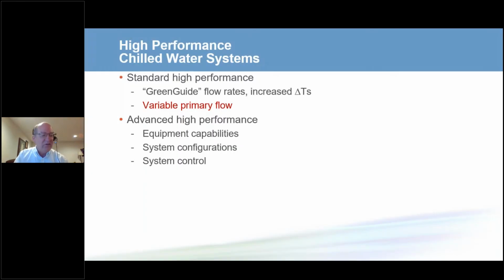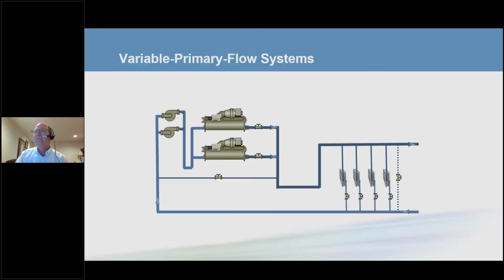The next thing we're going to talk about is, we talked about the normal performance chilled water system is a primary secondary system. Let's look at variable primary flow systems. In a variable primary flow system, what happens is rather than having 2 sets of pumps, we only have 1 set of distribution pumps, and we vary flow not only through the coils, but also through the chiller evaporators. Now, what I tell people, this is a 90-minute seminar. We're going to do it in about 4.5 minutes because our audience today is much smarter than most audiences. But what we're really going to do, we're going to just hit on the highest points. What are the most important parts about variable primary flow systems?